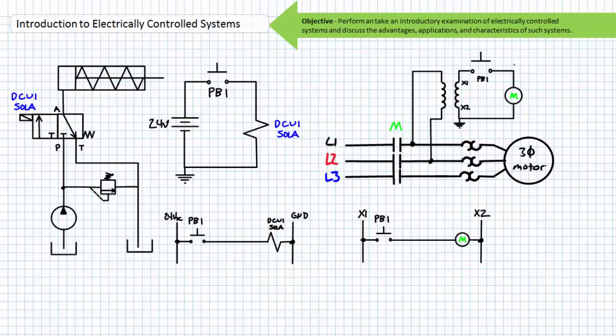One could use traditional schematics to draw the control portion of an electrically controlled system. However, in practice, this becomes very cumbersome for a complicated circuit, so the control schematic is ordinarily drawn using something called a ladder logic diagram. The low voltage output of the power supply or the control transformer is represented as the left and right side vertical upright rails of a ladder, and the conductive path from left to right is represented as a rung on that ladder. In the case of our electrically controlled hydraulic system, when push button 1 is closed, it completes a path from the high left side through the solenoid to the low right side.